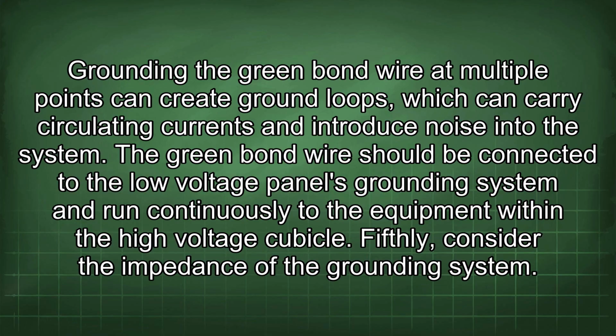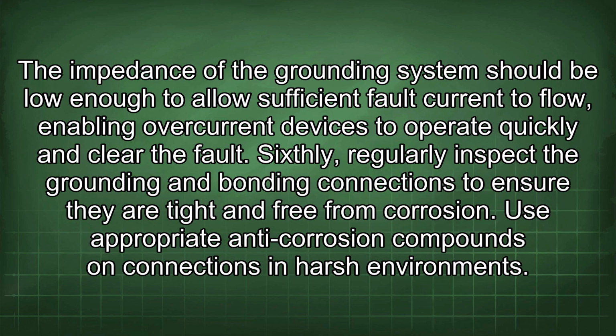Fifthly, consider the impedance of the grounding system. The impedance of the grounding system should be low enough to allow sufficient fault current to flow, enabling overcurrent devices to operate quickly and clear the fault. Sixthly, regularly inspect the grounding and bonding connections to ensure they are tight and free from corrosion. Use appropriate anti-corrosion compounds on connections in harsh environments.